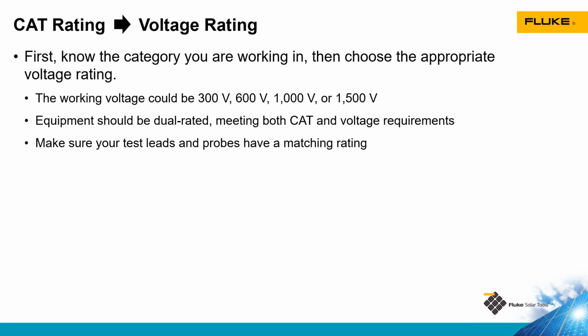Whatever test tool we're going to select must have the category rating and voltage rating above whatever voltage we're going to be testing at. So if I'm in a residential system, I'll need a Category 3 600 volt tool for the DC side. Commercial and industrial rooftop systems can go up to 1,000 volts, and then our utility scale systems at 1,500 volts. The last bullet that's up on the slide now is also really important.